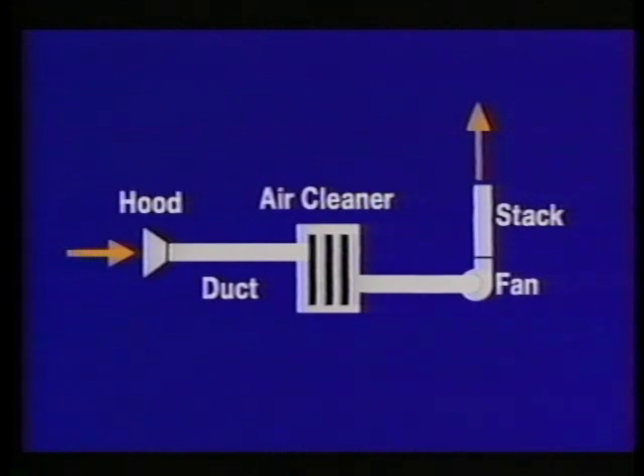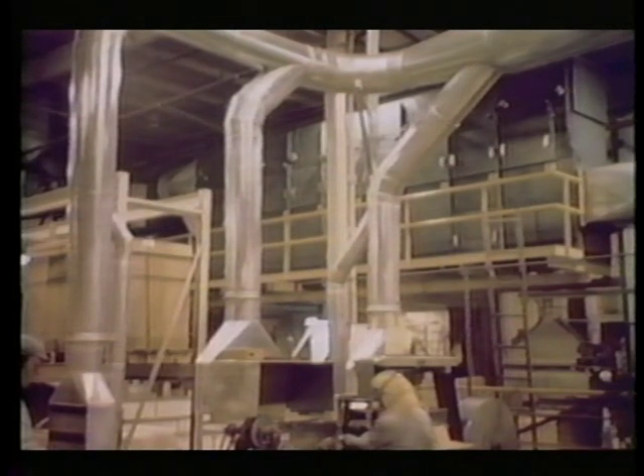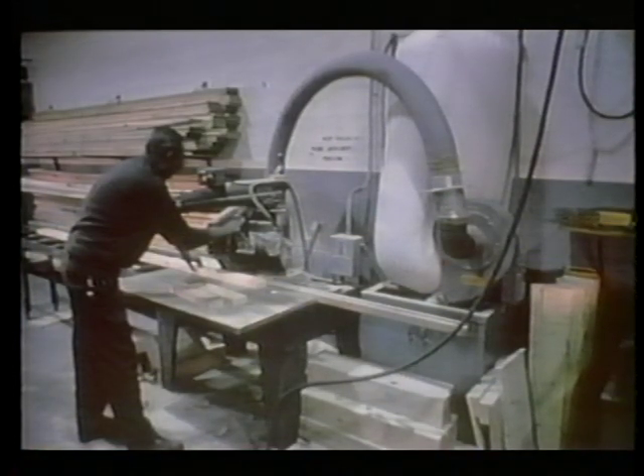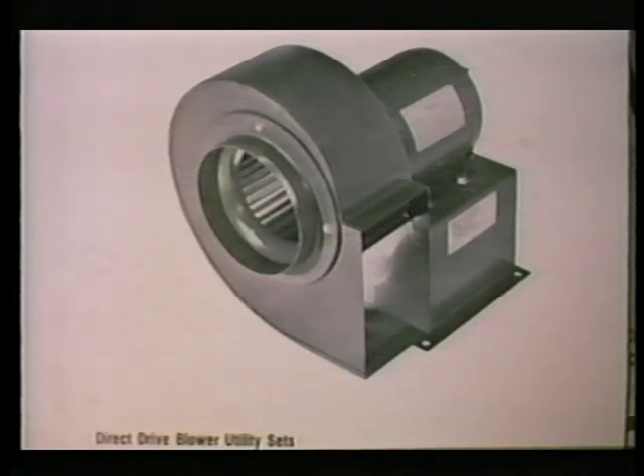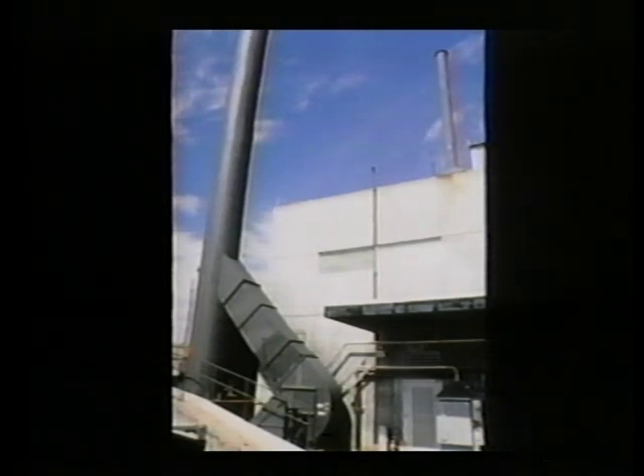The local exhaust system consists of five important components. It will work properly only if enough contaminants are captured by the hood so that concentrations in the workroom air remain below acceptable limits. The ductwork or piping transports the contaminants to an air cleaner or to the outdoor environment. Many local exhaust systems must be equipped with air cleaning equipment to meet air pollution requirements. The fan must develop enough static pressure to pull the desired amount of air and contaminants into the hoods and through the ducts. Finally, a stack is used to disperse the exhaust air stream and any contaminants that get past the air cleaner.